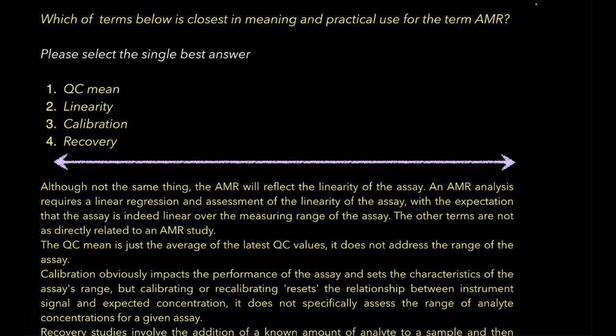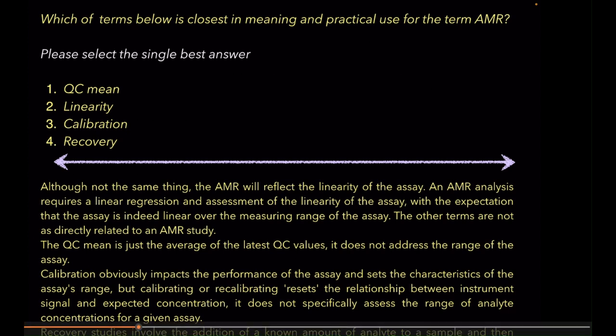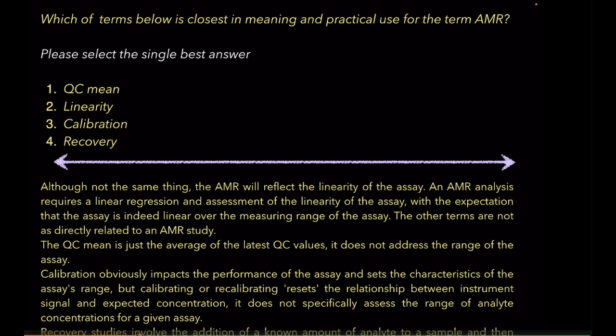The QC mean is just the average of the latest QC values, it does not address the range of the assay. Calibration obviously impacts the performance of the assay and sets the characteristics of the assay's range, but calibrating or recalibrating resets the relationship between instrument signal and expected concentration. It does not specifically assess the range of analyte concentrations for a given assay. Recovery studies involve the addition of a known amount of analyte to a sample and then determining what % of the amount added is detected.